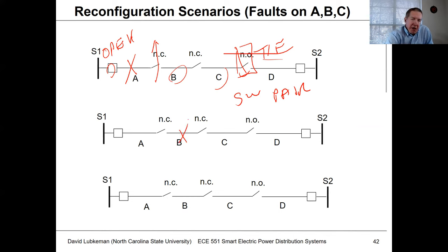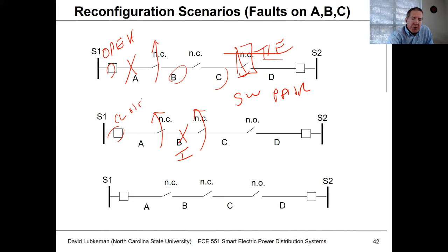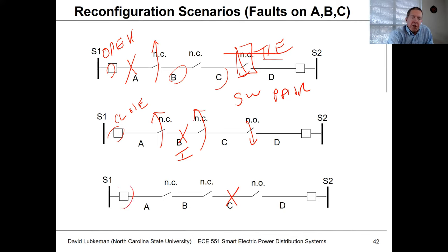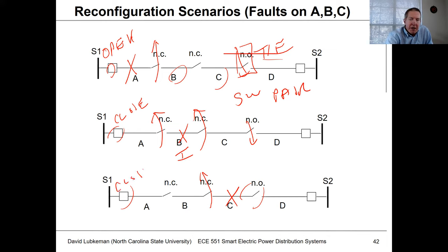If the fault is at B, the breaker locks open. I open the switch on each side — operating a switch pair — isolating that section. Then I can close the circuit breaker and also close the tie switch, which restores A and C even though B has to wait for the mean time to repair. Finally, if the fault is at C, I open the switch upstream of C, then close the breaker back in after it locked open, and A and B would have service while C has to wait.